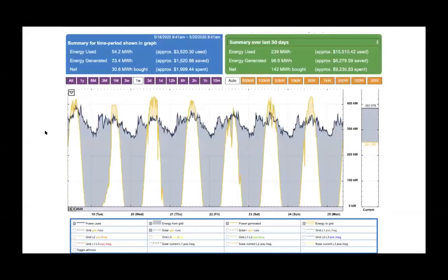The reason identifying these trends can be really helpful is that oftentimes utility rate structures are such that you will be subject to an increased fee if your peak demand exceeds a certain threshold. So eGauge monitoring can help identify when that peak demand happened, and you have the ability to adjust your operation to decrease that peak demand and realize financial savings there. The same thing with base load.